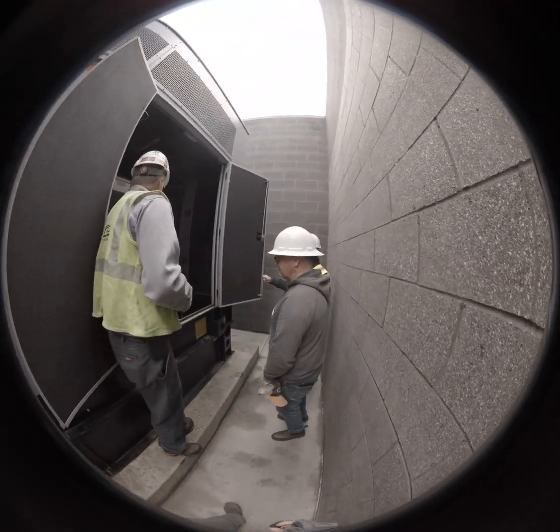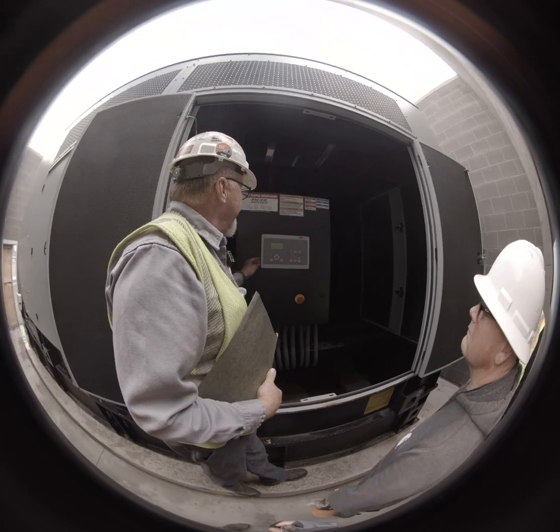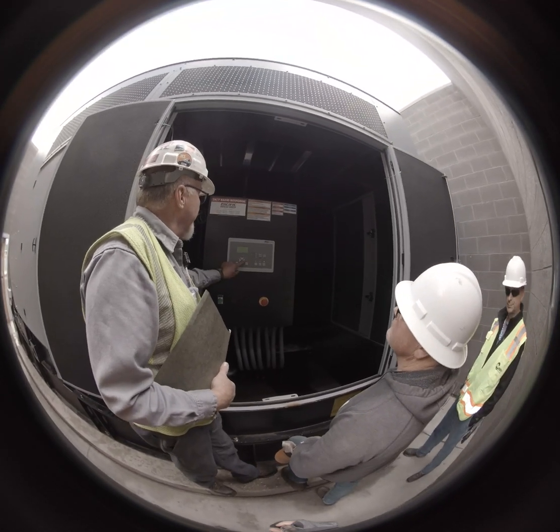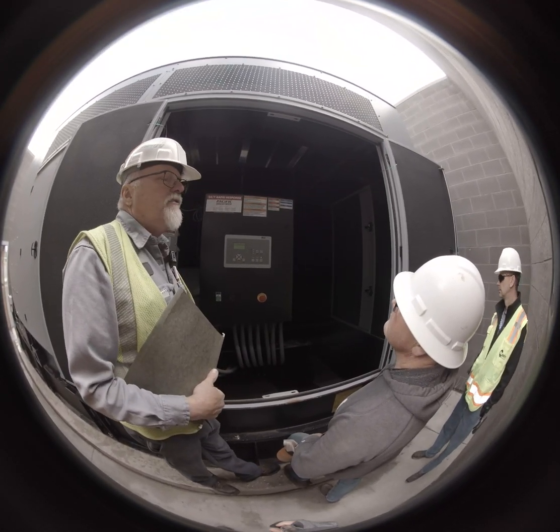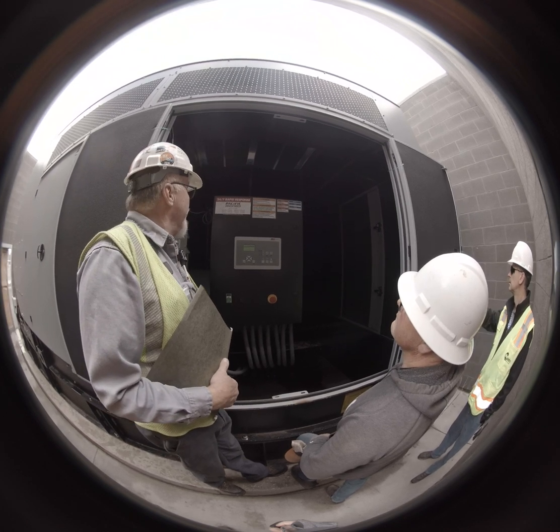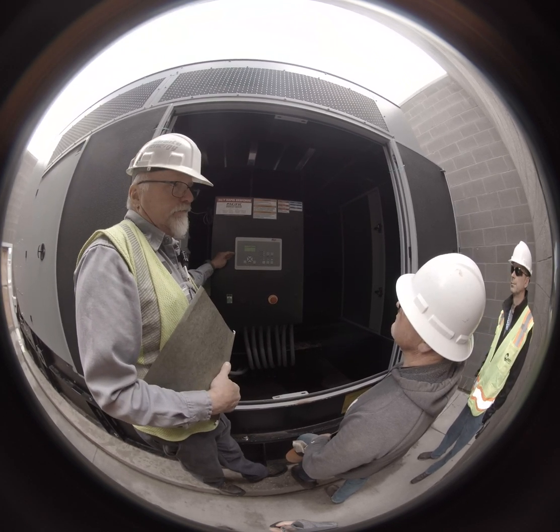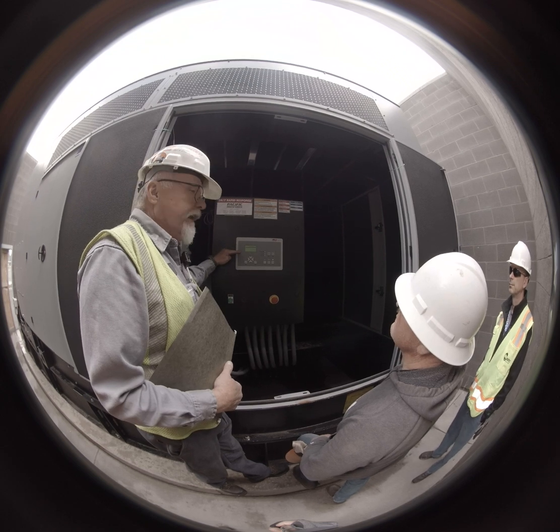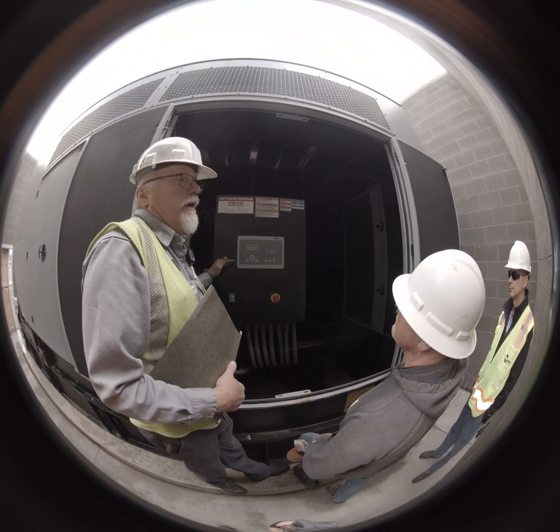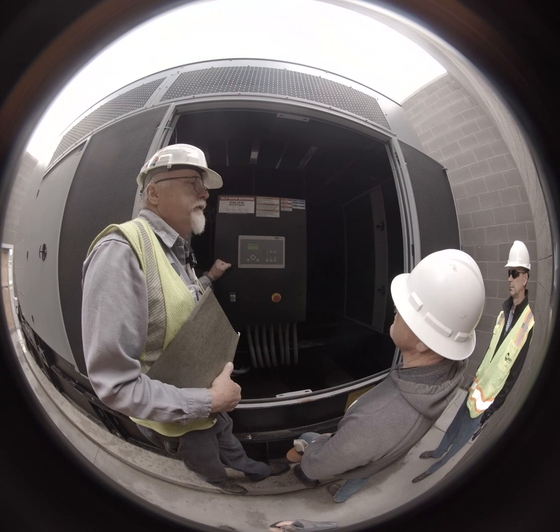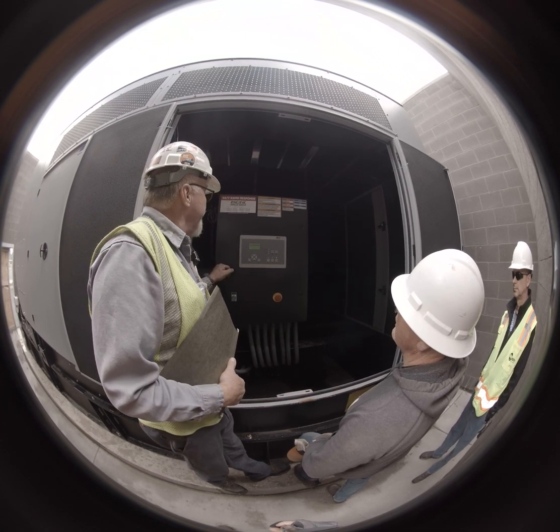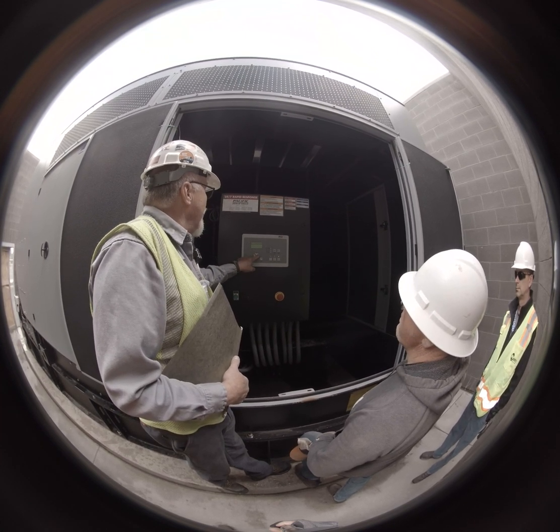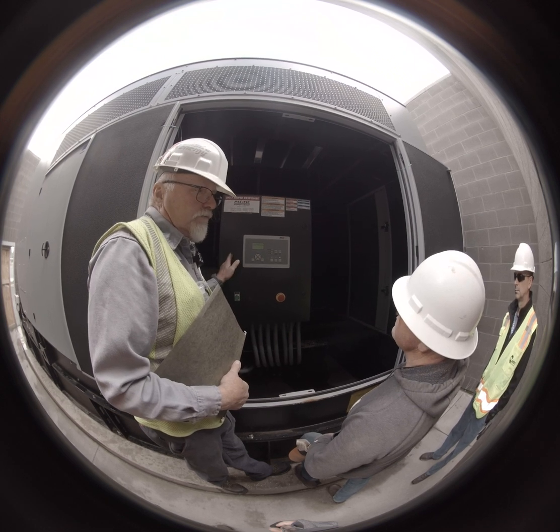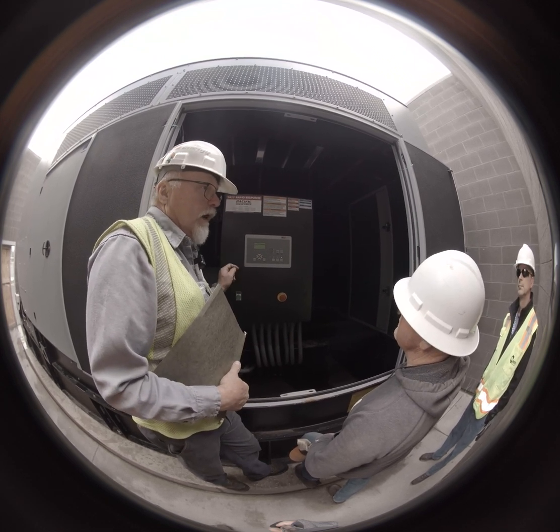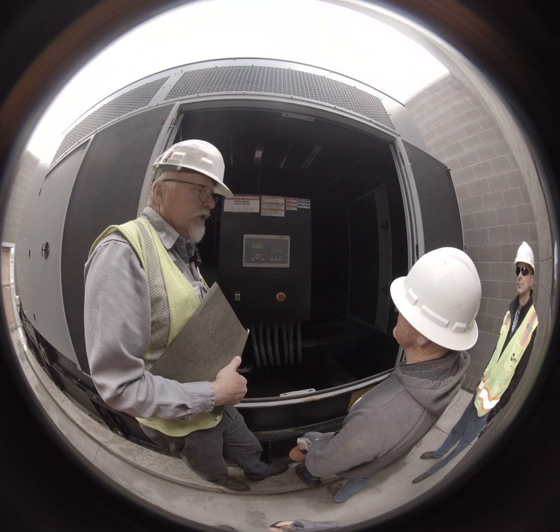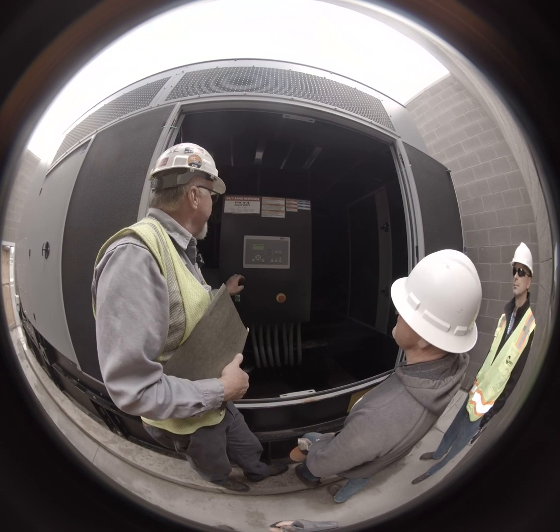Okay, so control panel. Right now we're sitting on our base screen. So we walk our arrow over. Now you see these two sets of menus that we were talking about. We have metering and we have settings. Okay, the settings, like I said, are parameters that we put in there or the factory puts in there for this machine to operate. So go to would be exercise. Exercise comes out of the transfer switch. It can come out of this, but we typically put the exercise into the transfer switch. And we'll get to that inside. Okay.